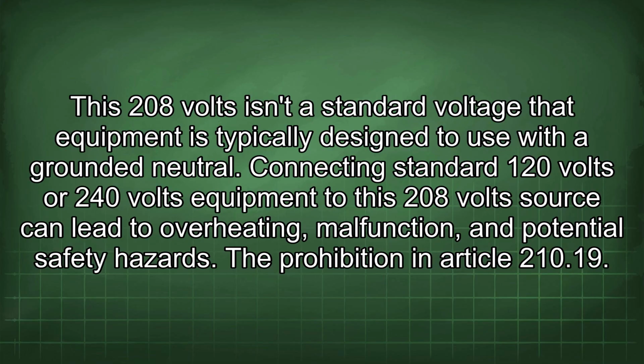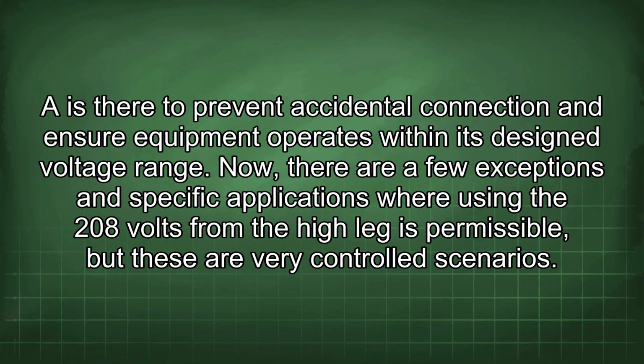This 208 volts isn't a standard voltage that equipment is typically designed to use with a grounded neutral. Connecting standard 120 volts or 240 volts equipment to this 208 volts source can lead to overheating, malfunction, and potential safety hazards. The prohibition in Article 210.19 is there to prevent accidental connection and ensure equipment operates within its designed voltage range. Now, there are a few exceptions and specific applications where using the 208 volts from the high leg is permissible, but these are very controlled scenarios.